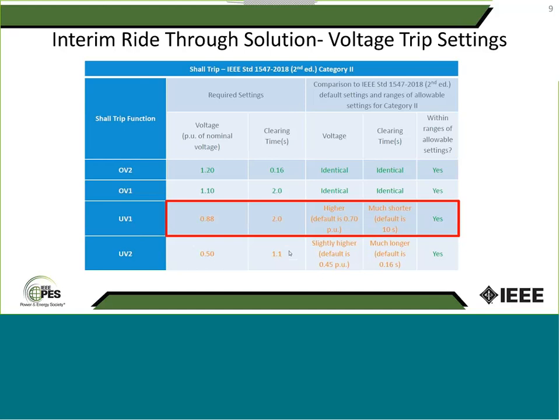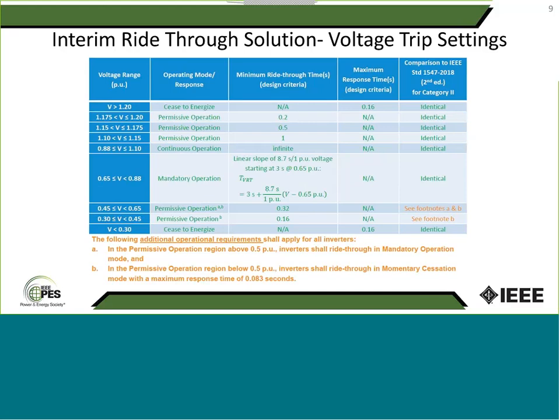Without that momentary cessation, there's a challenge. For example, with rotating machines, if you're in a state where the penetration of rotating generation is high, you may be concerned that these generators staying on for a long time during an under voltage condition may have an impact on system protection. So you may need to require some sort of power line carrier technologies or something that would be used to detect distribution faults in addition to overcurrent protection. So with that, I'm going to move on to the next slide.